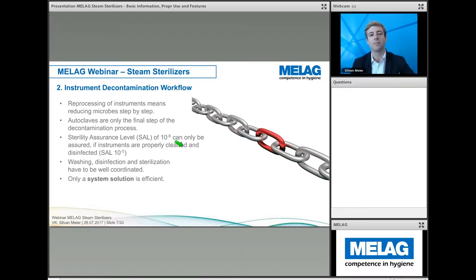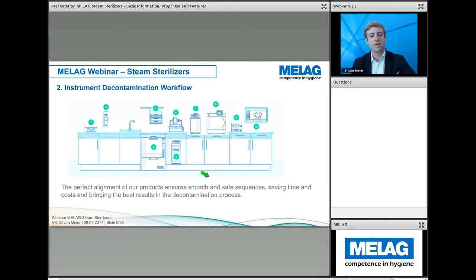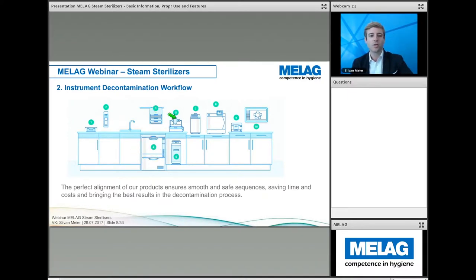If one link is missing, we don't have successful sterilization of instruments — only a system solution is efficient. Here we have a model of an instrument decontamination workflow. We start with pre-washing with disinfection, then number three is our loading system, the Melastore system, which can be used throughout the decontamination process — starting from automatic cleaning and disinfection through to sterilization.